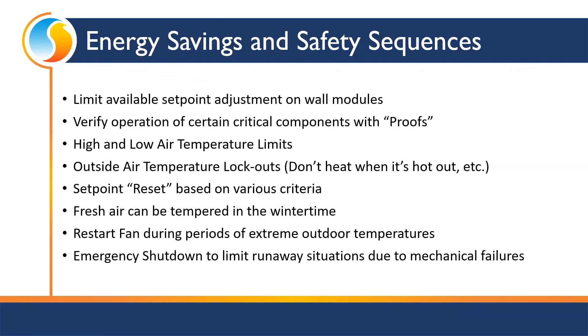We have emergency shutdowns to limit runaway situations. Say again, back to that situation, demand controlled ventilation. We open the damper, bringing stuff in, then something decides to break, and now we can't physically close the damper, and the heat's gone out, and the boiler's not running, so we can't heat the air. Well, we can identify that, hey, we've lost control of this unit. We need to shut everything down to protect the building.